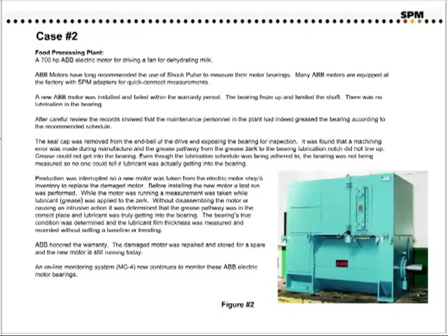There was no lubrication in the bearing. After careful review, the records showed that the maintenance personnel had indeed greased the bearing according to the recommended schedule. The seal cap was removed from the end-bell of the drive end, exposing the bearing for inspection. It was found that a machining error was made during manufacture, and the grease pathway from the grease zerk to the bearing lubrication notch did not line up. Grease could not get into the bearing. Even though the lubrication schedule was being adhered to, the bearing was not being measured, so no one could tell if lubrication was actually getting into the bearing.